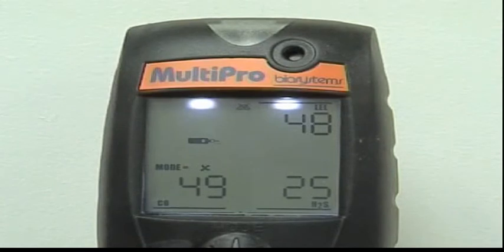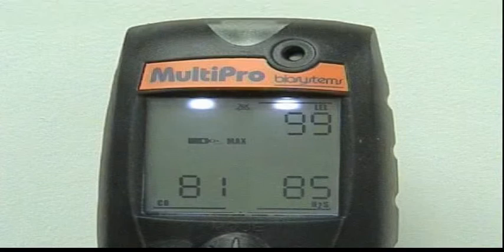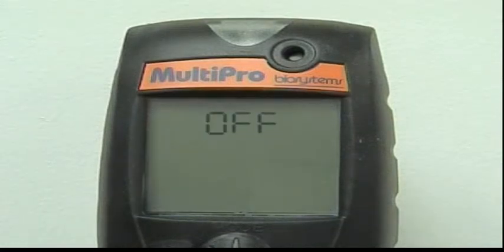Once the calibration of the LEL and all toxic sensors is successfully completed, the instrument will briefly show the maximum adjustment values screen. The maximum adjusted values for the LEL and toxic sensors give an indication of the relative health of the sensors. As a sensor loses sensitivity, the maximum possible adjustment will decrease to approach the expected concentration of the calibration gas. When all sensors installed in the MultiPro have been adjusted, the instrument will shut itself off. Disconnect the calibration assembly prior to turning the instrument back on.